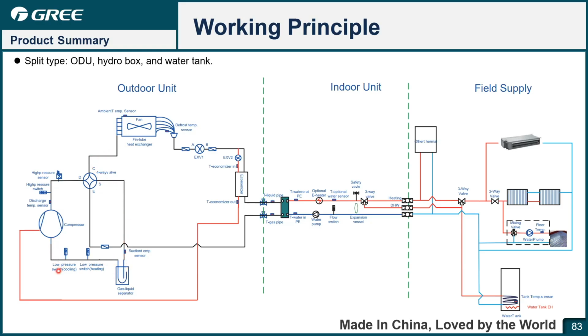sucked by the compressor. And for the VERSATI 3, there are two pressure switch, one for cooling and heating because of the working value. For different conditions, they are different. So we set two pressure switch. Okay, that's the refrigerant circulation.